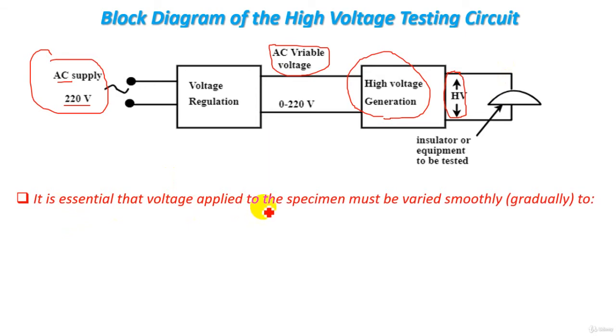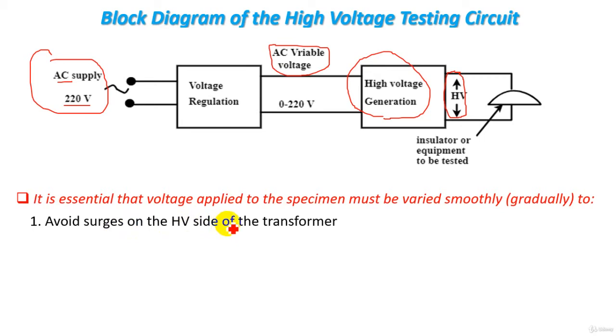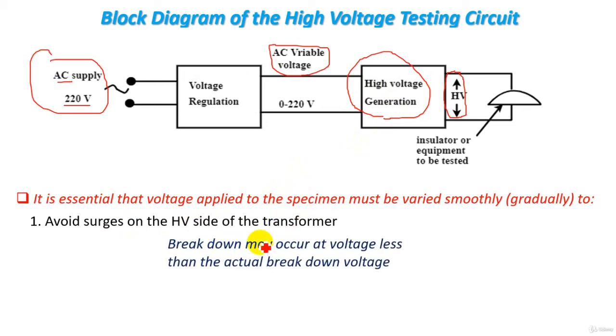It is essential that the voltage applied to the specimen or equipment must be varied smoothly and gradually. Why? We should vary the voltage smoothly and gradually in order to avoid voltage surges on the high voltage side of the transformer — since the high voltage generation stage is essentially a high voltage testing transformer. If the rate of change of voltage is very high, surge current may flow and breakdown may occur at a voltage less than the actual breakdown voltage.